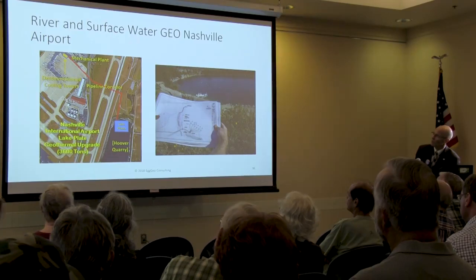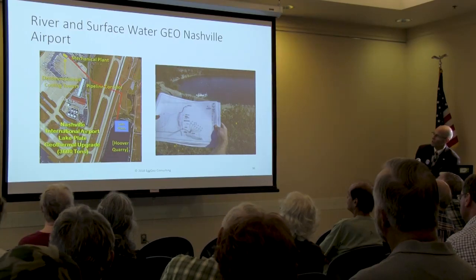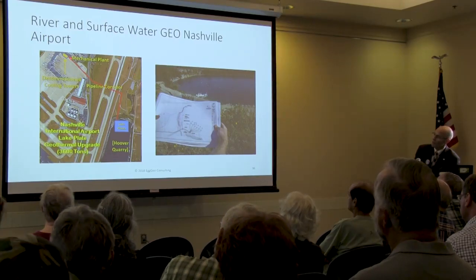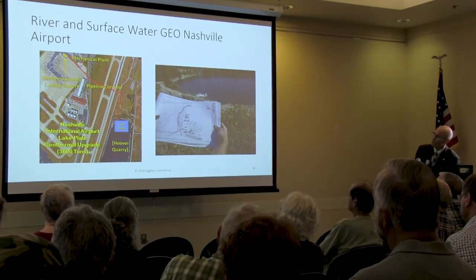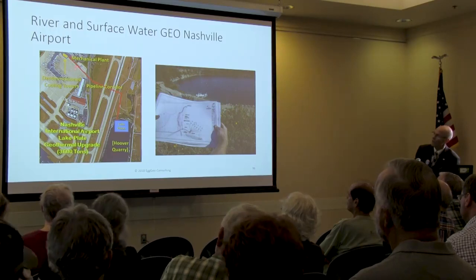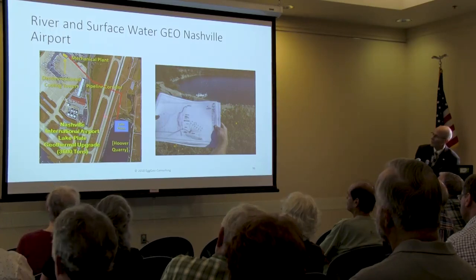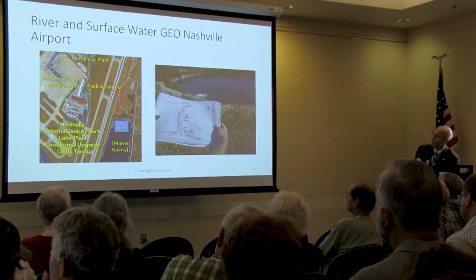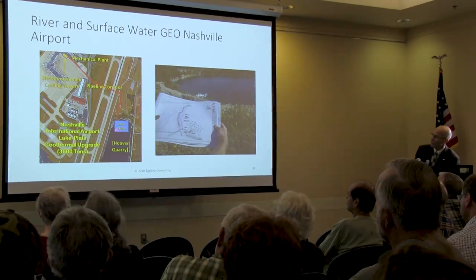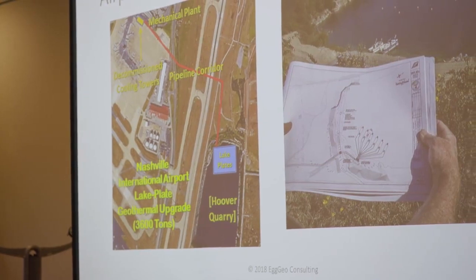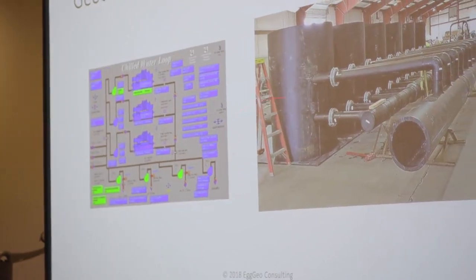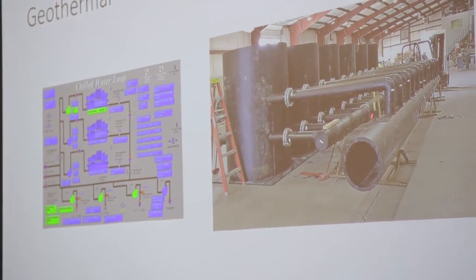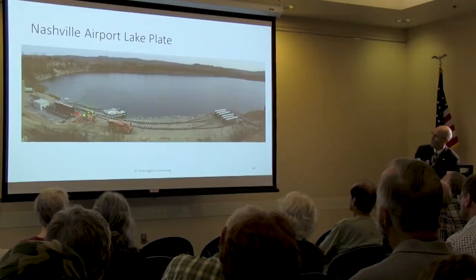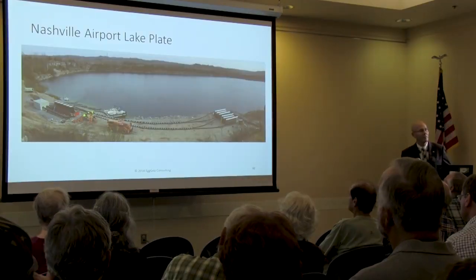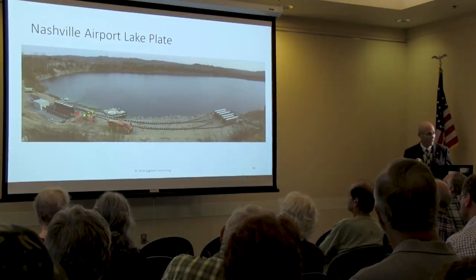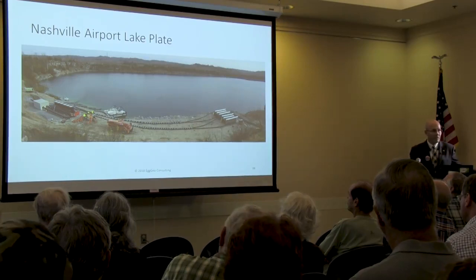This is an example of river and surface water geo in Nashville. They had a 3,900 ton, they still do have a 3,900 ton chiller plant, and they bored all the way over to this Hoover Quarry, and they put in these lake plate exchangers into this chiller system using this header system, and they eliminated their cooling towers and all of their natural gas. I mean, they're doing it all the time.